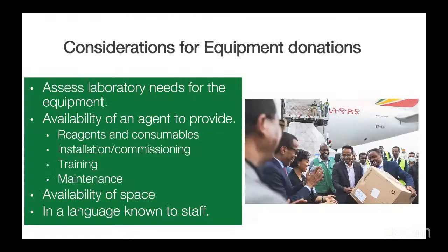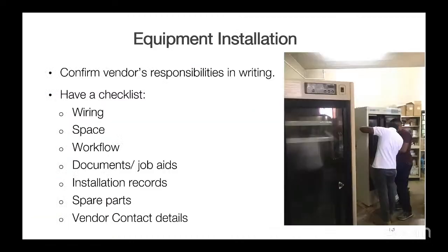What are the considerations for equipment donation? Assess the laboratory need for the equipment, availability of reagents and consumables, installation, commissioning, training, maintenance, availability of space. Also, is it in a language known to the staff? Some equipment has its interface in certain languages, and if the equipment does not have the language you are used to, you need to look at those things.